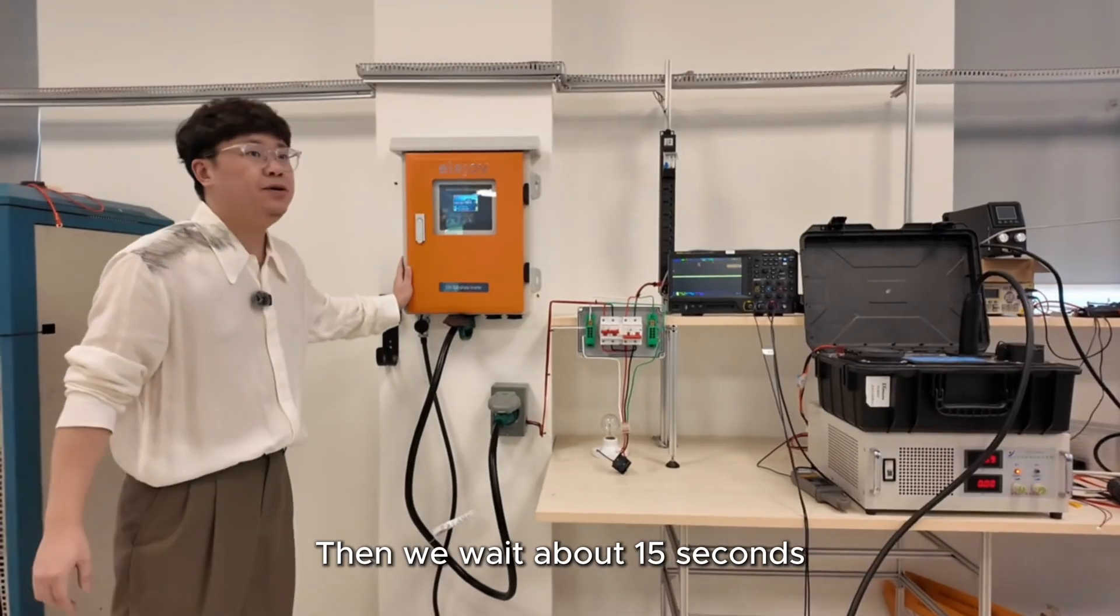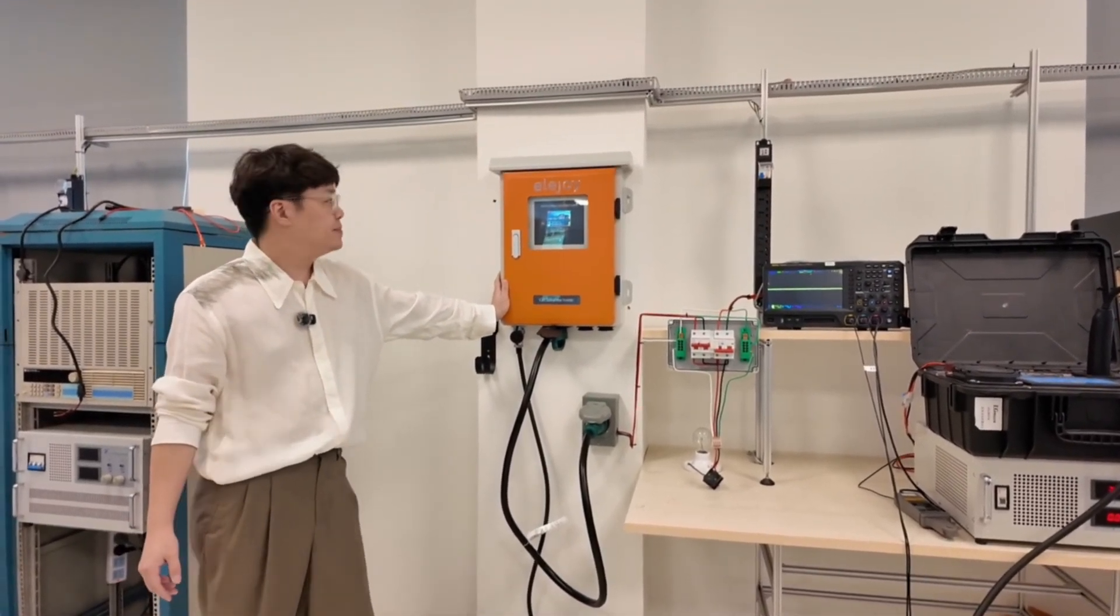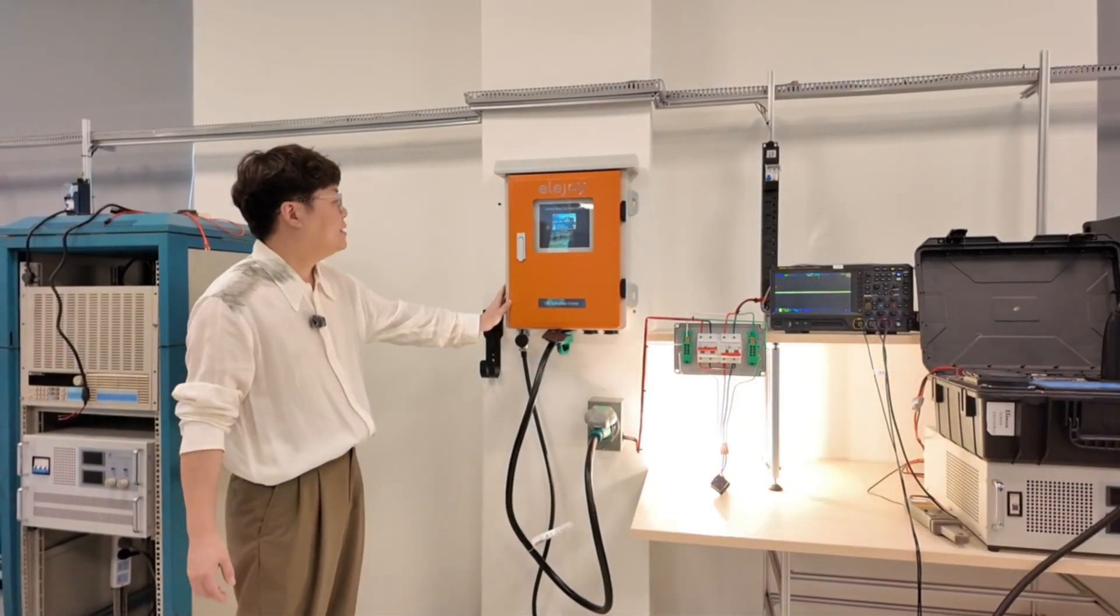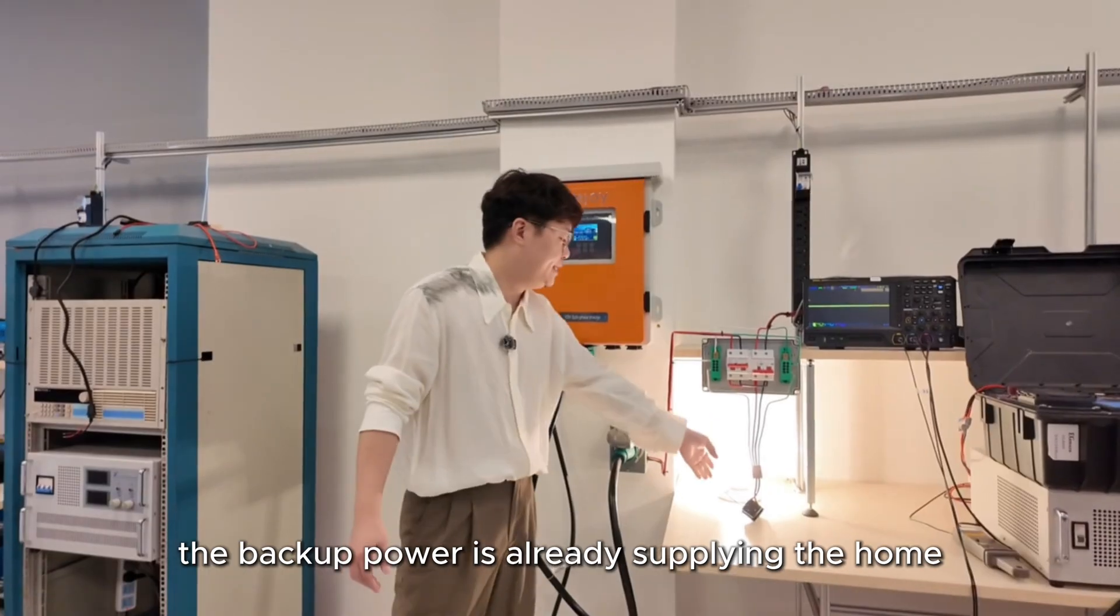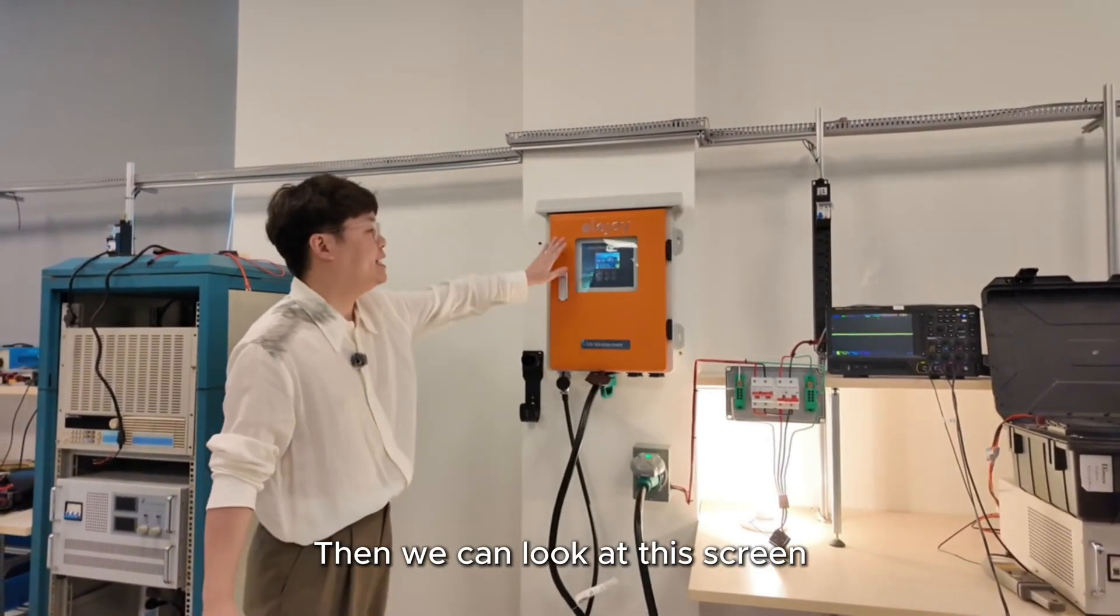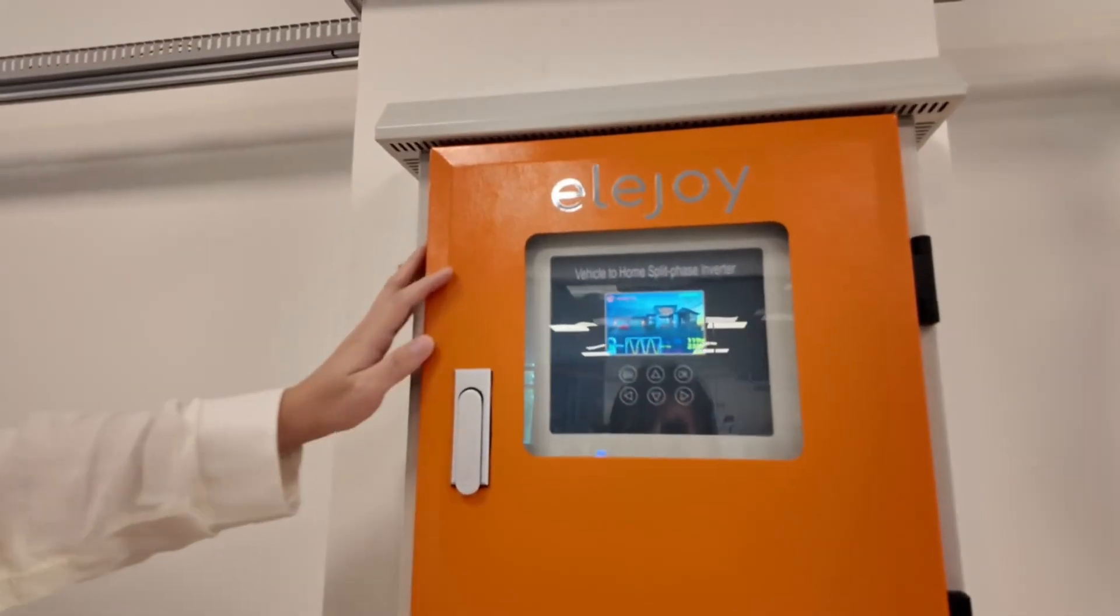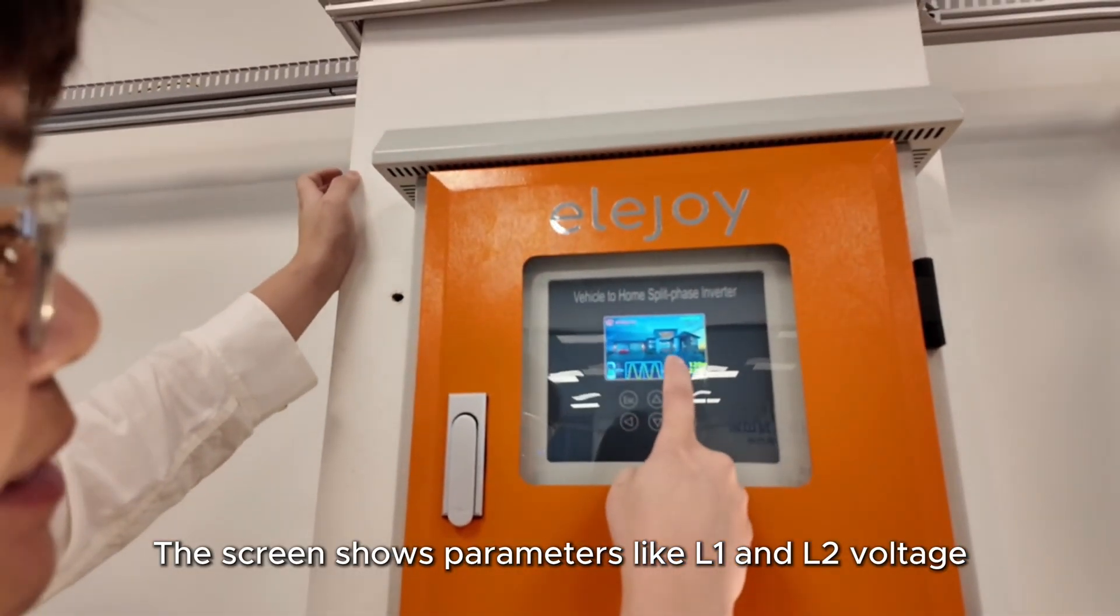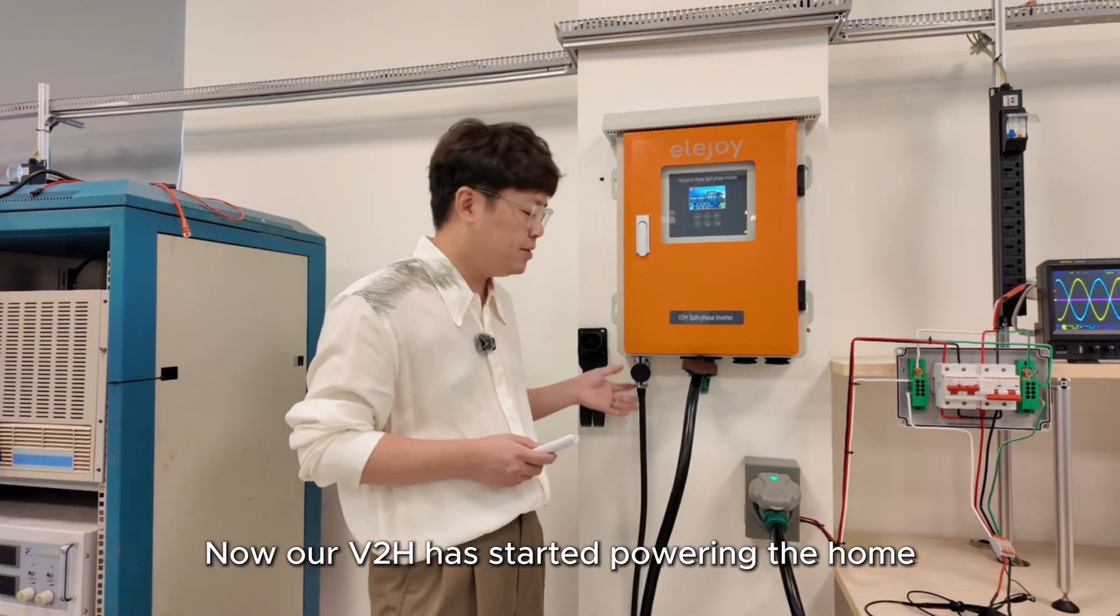Then we wait about 15 seconds. The V2H will connect with the vehicle. At this time we can see the backup power is already supplying the home. Then we can look at this screen. The screen shows parameters like L1 and L2 voltage. Now our V2H has started powering the home.